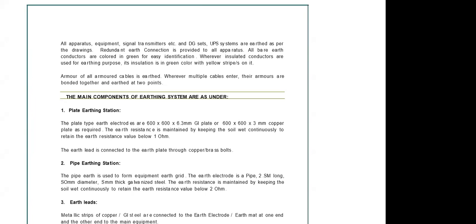This is a 600 by 3 mm GI plate, 6 mm GI plate, or a copper plate of the same dimension. But generally nowadays we avoid copper because of theft and pilferage cases. But the purpose is the same. The one thing is that as far as conductivity is concerned, you have to decide what will be the dimension of the GI plate for a particular earth fault, and compared to that, what will be the copper plate. The earth resistance in both the cases has to be less than 1 ohm.